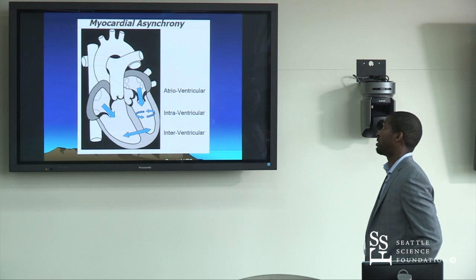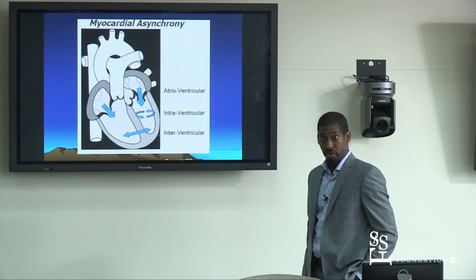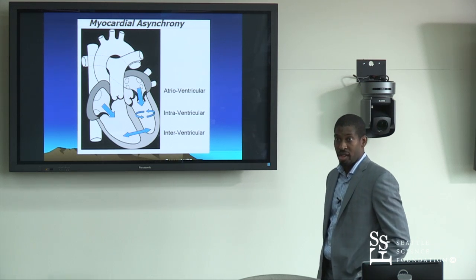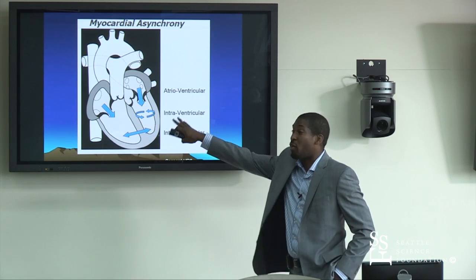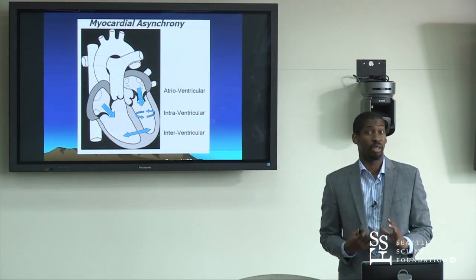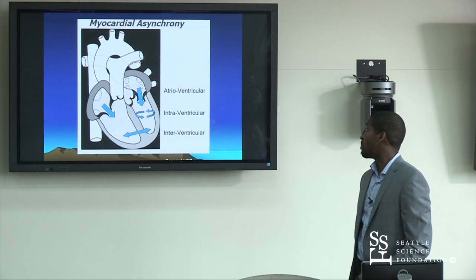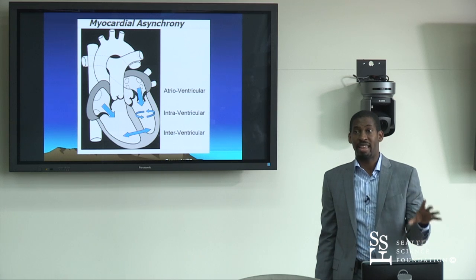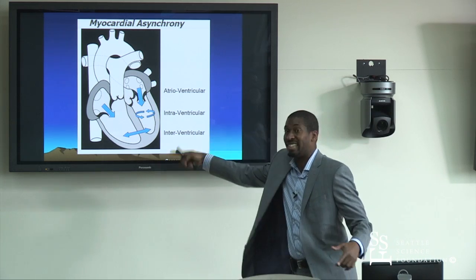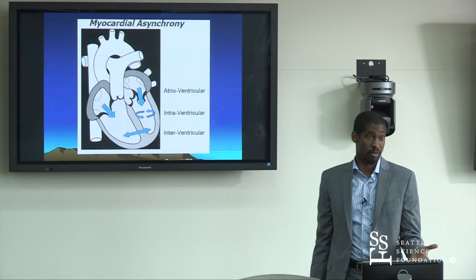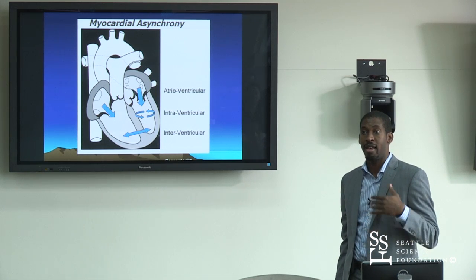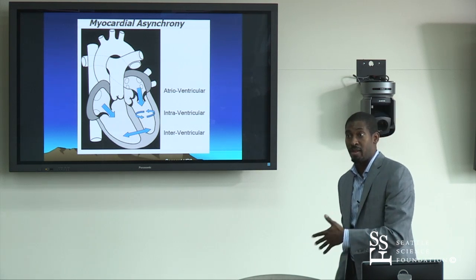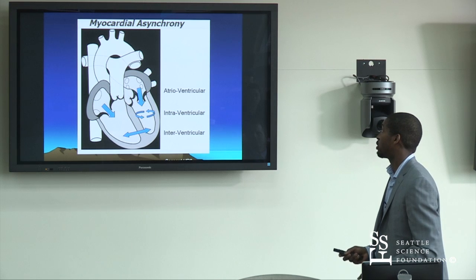When talking about dyssynchrony, there's atrioventricular synchrony between atrium and ventricles, LV-RV dyssynchrony, and dyssynchrony within the LV itself — all interrelated. Probably the most powerful parameter we can control is AV synchrony. By adjusting AV timing appropriately, you can fix a lot of the dyssynchrony. That's really been the focus of device company algorithms — optimizing that AV interval to provide the best overall global synchronous contraction.